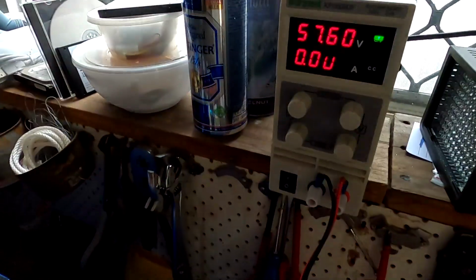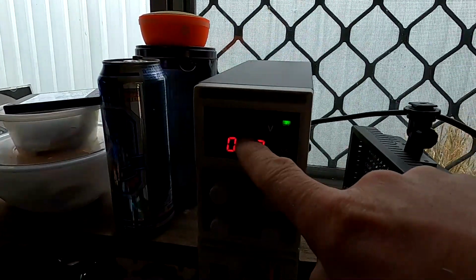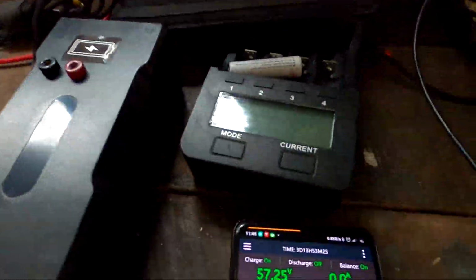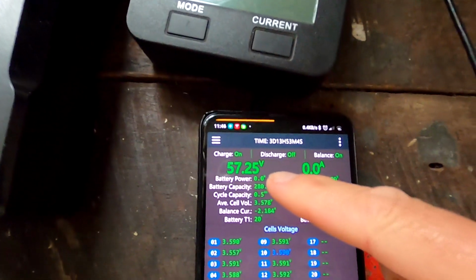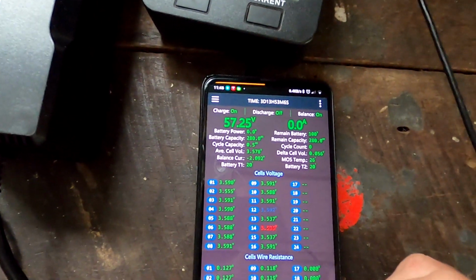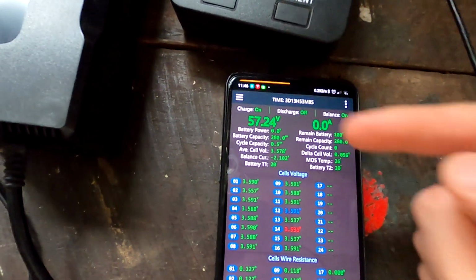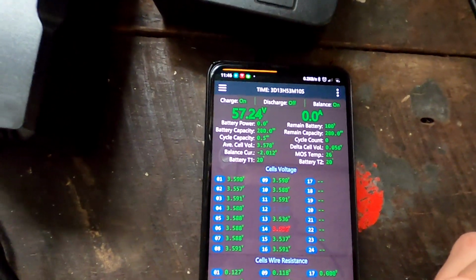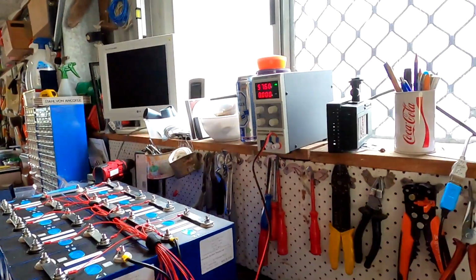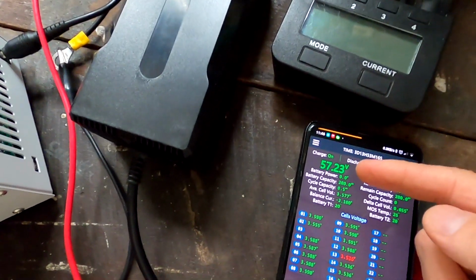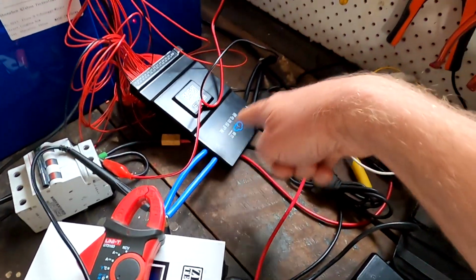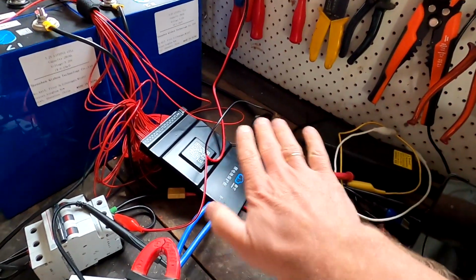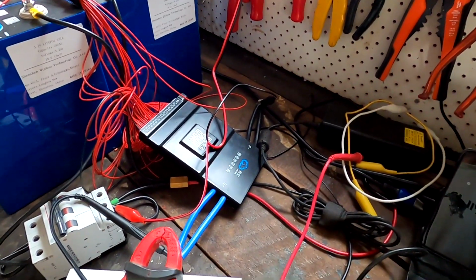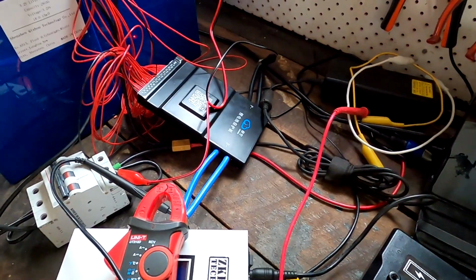Well, and there we have it: 57.6 I have set, but the battery has already turned off at 57.25, no current flowing anymore. The whole process has stopped 0.4 volts below the set voltage of the power supply. The remaining 0.4 volts can be measured across the BMS now with no current flowing at all. That is not correct.